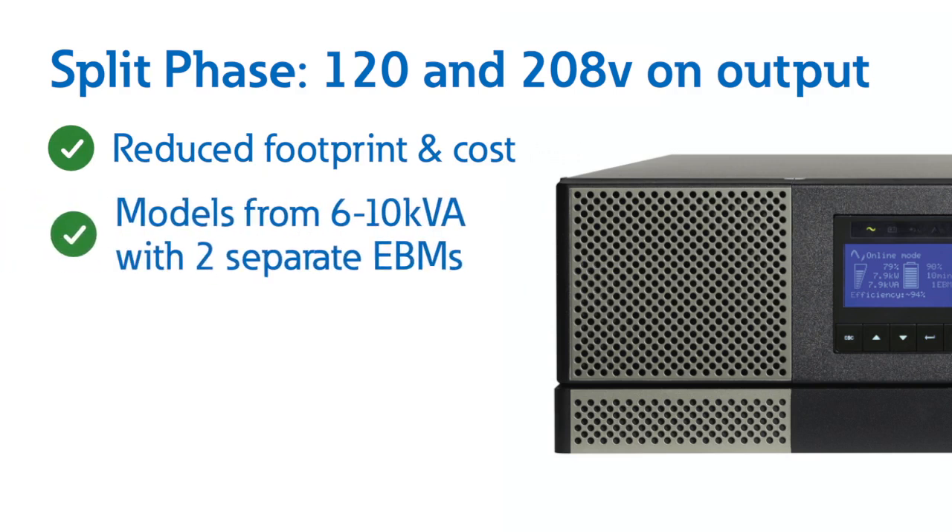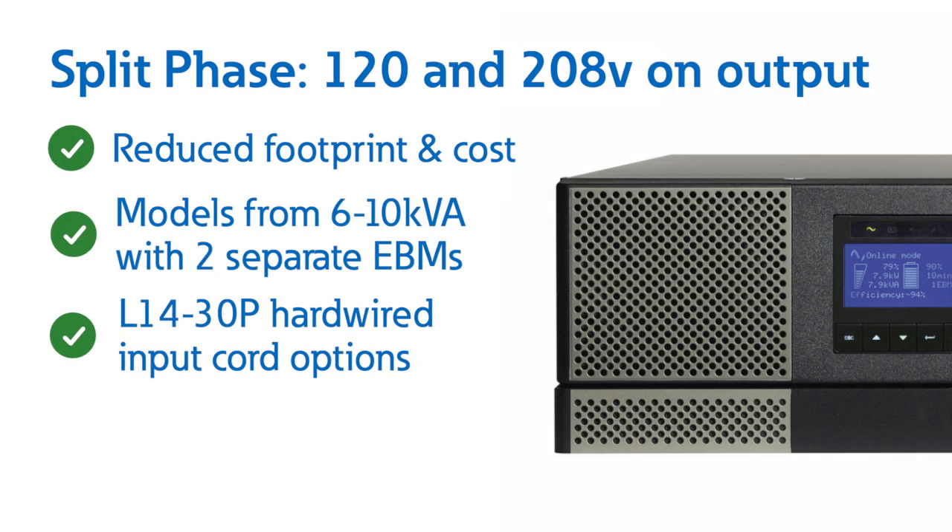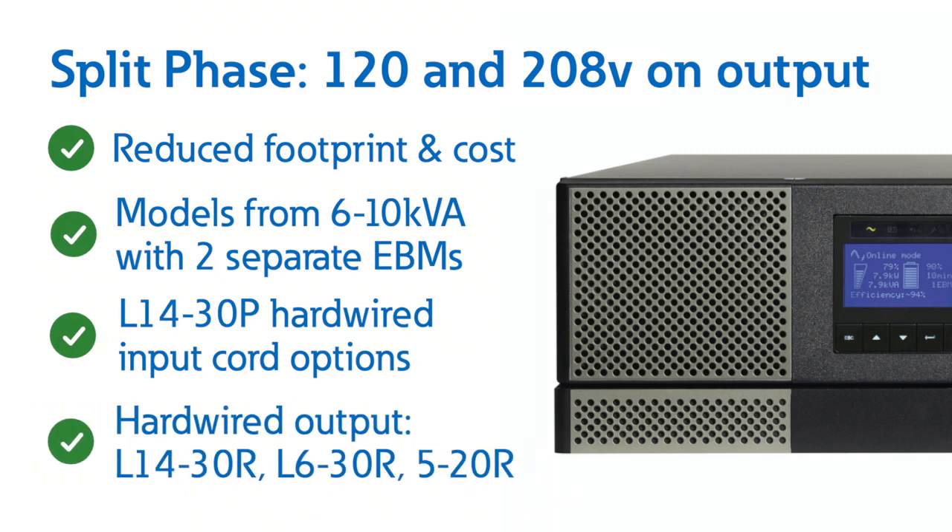We have three models available ranging from 6 to 10 kVA with two separate EBMs for extending runtime. The input cord options are L14-30P and hardwired. There is lots of versatility with our output receptacles which include L14-30R, L6-30R, 5-20R, and hardwired.